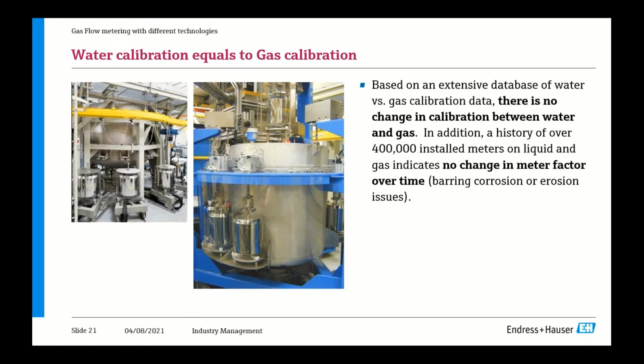Although this methodology requires that the meter be removed from service, it defines a very accurate in situ performance of the meter, since steps 1 and 2 establish the meter traceability between water and gas, and verifying water performance in step 3 automatically verifies it. In that way, of course, you get a more stable, very good performance device in gas applications.